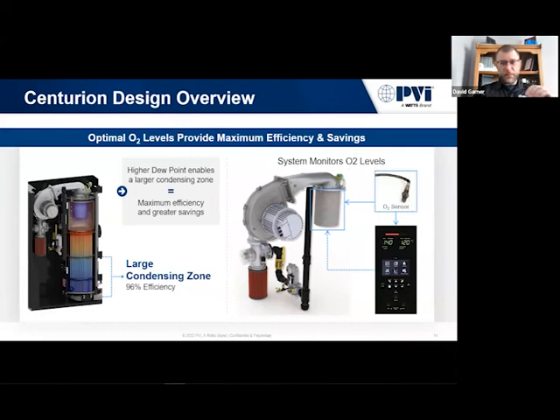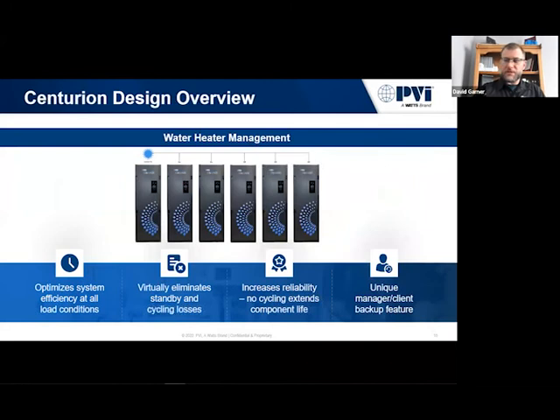If we can tweak the blower just by a couple RPMs, that's going to allow us, up or down, to make sure we have that perfect air-fuel ratio that we need to maintain. It depends on the firing rate, but I believe it's 5% to about 7% O2 to make sure that we're burning all the natural gas and we're operating in a safe condition. In addition, going back to the efficiency curves, we're going to make sure we're utilizing as much of that heat exchanger as possible to condense and get all that energy that we're putting into the unit.